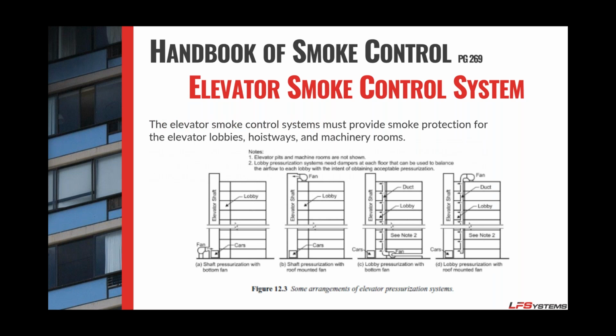Just a few diagrams, simple layouts. The left 2 show a fan with a single injection into the shaft. One's at the bottom, one's at the top. The right side are actually pressurizing the lobby of the elevators to maintain smoke, so you can't get smoke infiltrating into the lobbies. This is a great option if you're using an evacuation plan with the elevators, because now you have a safe space waiting for the elevator rather than just standing in the corridor.